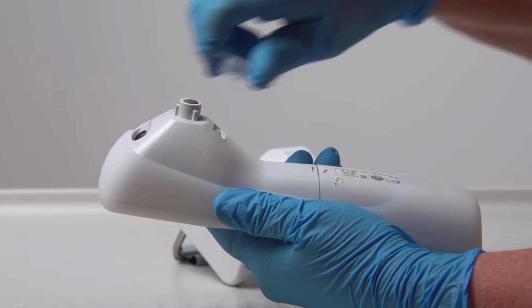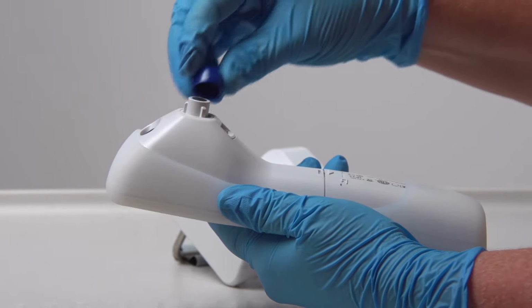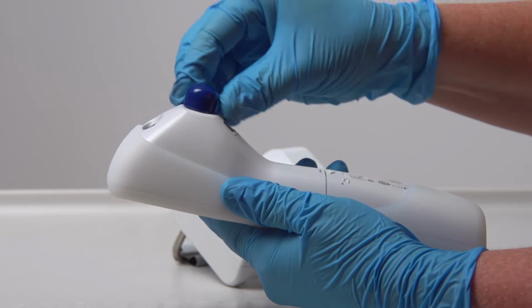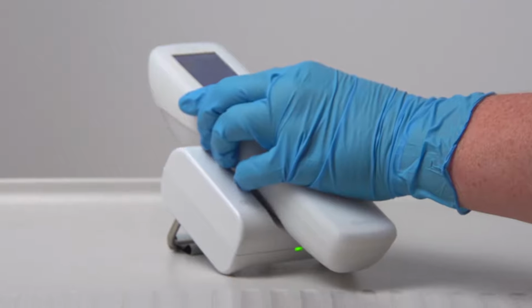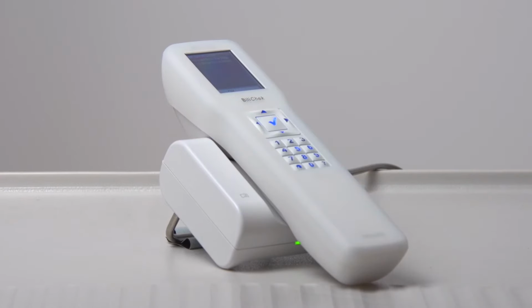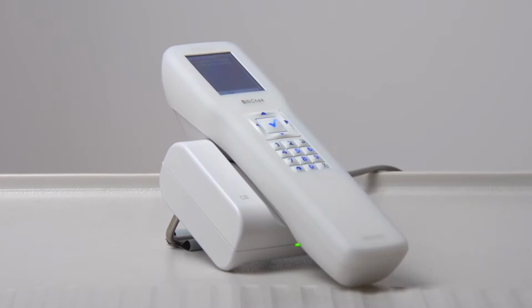Remove and dispose of the BiliCal tip and apply the protective blue plug. Then return the handheld unit to the charger base. If your device is configured to transmit data to a lab information system or electronic medical record system when the handheld unit is returned to the charger base, all records since the last data transmission will be sent.